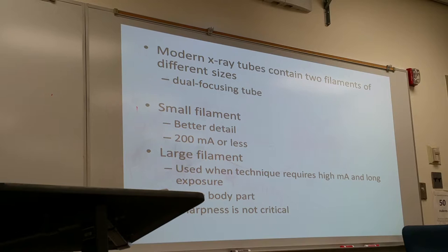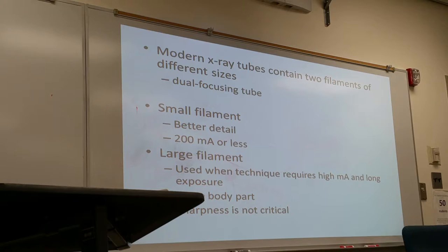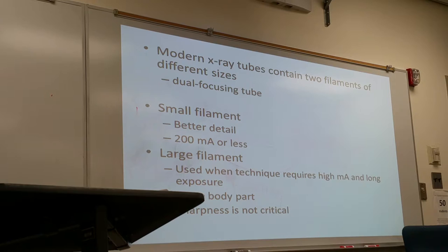The larger filament is used mainly for bigger body parts such as the abdomen and skull, while the small filament is mainly used for extremities like the foot, knee, and hand. The benefit of using a larger filament is that it can withstand high heat, so we can use high mA stations and longer exposure times. The downside is that resolution decreases slightly — you can't really see it with the naked eye, but quality tests show degraded sharpness. So a large filament gives high exposure but lower resolution.